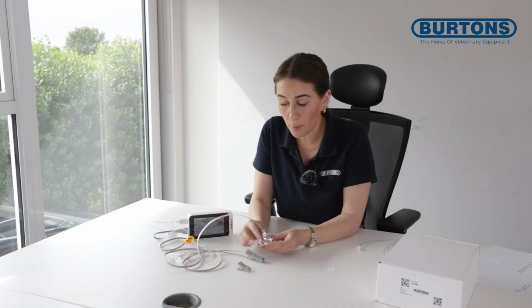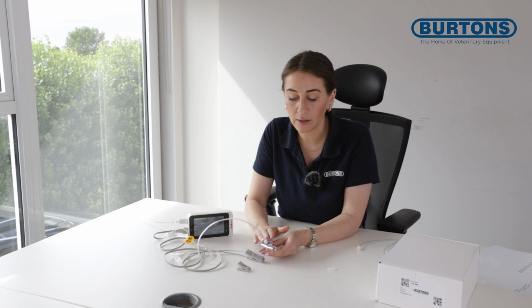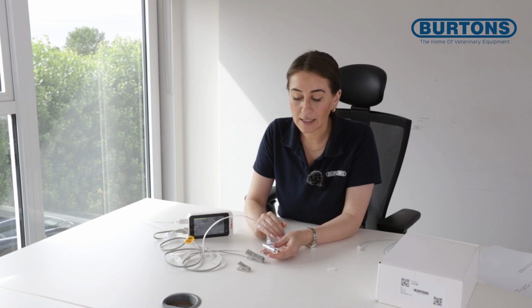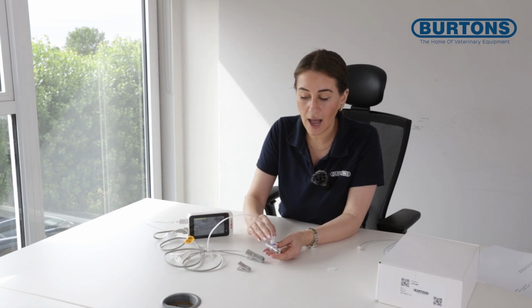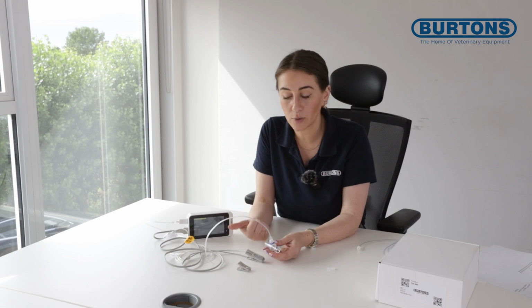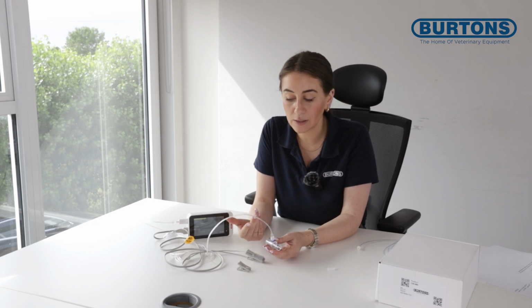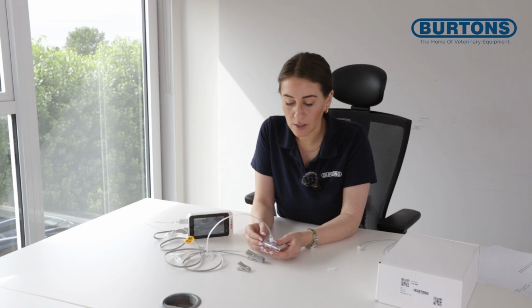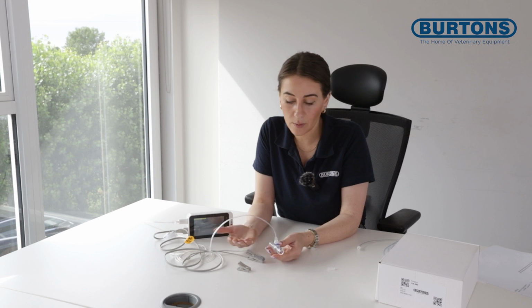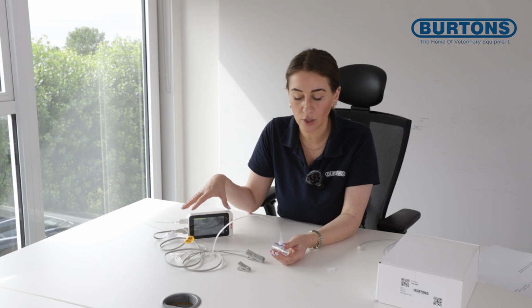So the pump of the machine is actively pulling from the patient's breath, and it's important to note that as it pulls, it's pulling not only CO2, a certain degree of oxygen, our inhalational agent as we discussed earlier, but also the water vapor that the patient expires. So whilst it's pulling, we want to try and prevent water vapor from entering the machine as much as possible.